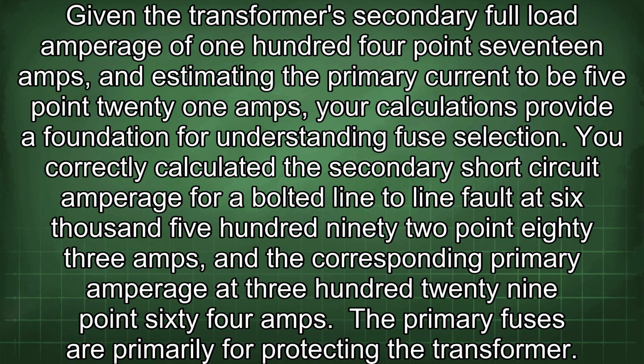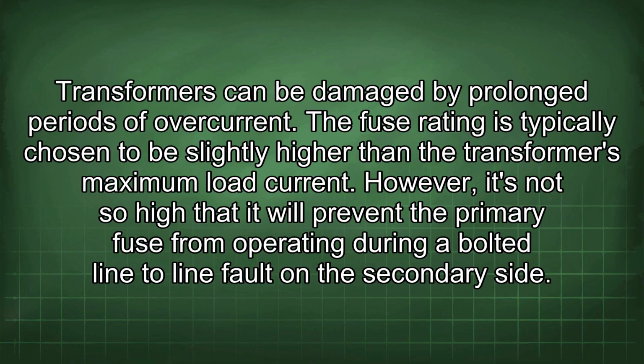You correctly calculated the secondary short circuit amperage for a bolted line-to-line fault at 6,592.83 amps, and the corresponding primary amperage at 329.64 amps. The primary fuses are primarily for protecting the transformer. Transformers can be damaged by prolonged periods of overcurrent.